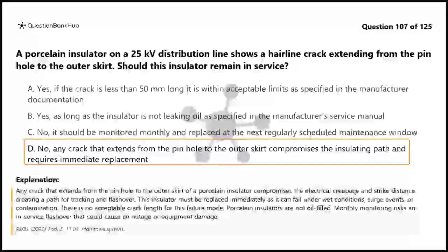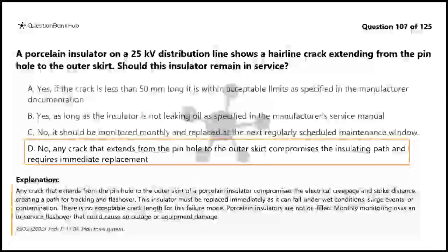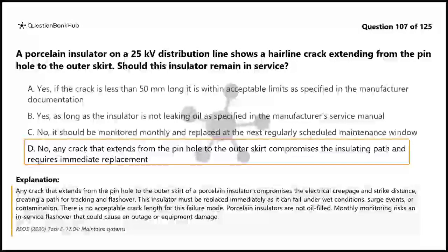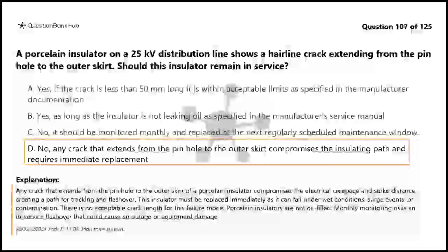The correct answer is D. Any crack that extends from the pinhole to the outer skirt of a porcelain insulator compromises the electrical creepage and strike distance, creating a path for tracking and flashover. This insulator must be replaced immediately as it can fail under wet conditions, surge events, or contamination. There is no acceptable crack length for this failure mode. Porcelain insulators are not oil-filled. Monthly monitoring risks an in-service flashover that could cause an outage or equipment damage.